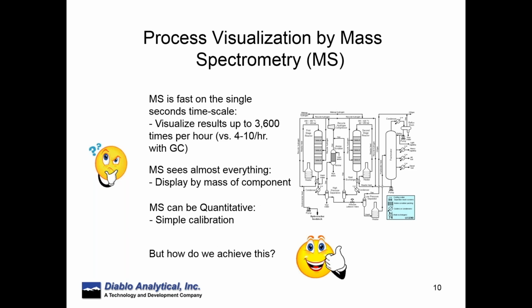So if you take mass spectrometry on its face, it's looking at the mass to charge ratio of a fragment from each component. It's linear up to four orders of magnitude of dynamic range, and it can operate very fast in the single second acquisition timescale. So if you're getting a data point every second, you can see up to 3,600 times per hour with a mass spec, where maybe you would get a data point between 4 and 10 times per hour with a gas chromatograph.